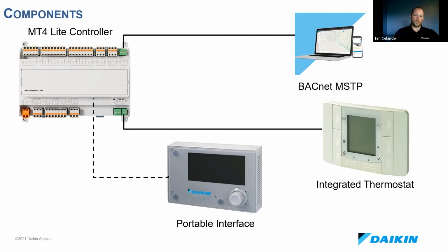You can control your schedule, and it's monitoring the space temperature that we'll be controlling to for most of the control selection options. The portable user interface in the bottom is meant to be either one or two for a job site, or maybe the servicer of that building. What this is going to do is plug into an external Ethernet port on the PreciseLine and give you full access to all of the set points, including the scheduling, including fan speeds, etc., being able to read alarms and read the performance of the unit. So it's helpful for troubleshooting and critical for startup.